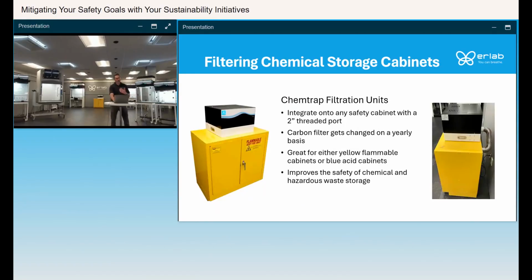And then we also have, since all of you, I'm sure, have yellow flammable safety cabinets or blue acid cabinets in your lab or in your building, a ChemTrap filtration unit that will integrate onto those cabinets. All those cabinets typically have a 2-inch threaded port, so you can connect metal tubing from that cabinet to our ChemTrap filtration unit, which has a fan and a carbon or a HEPA filter in it to remove the chemical fumes or vapors that are being released in those cabinets.